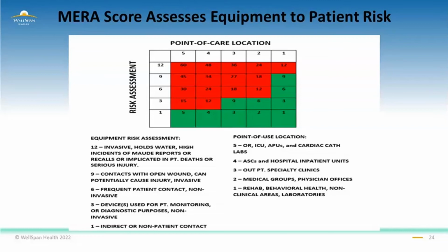First, MERA assesses the equipment to patient risk by choosing the multiple which best aligns with the equipment's components and its physical contact with the patient. Based on our equipment review, we know that the equipment holds water in a humidifier reservoir per the manufacturer's instruction manual. So we begin at the left column of the chart reviewing the categories. We assign the equipment risk number a 12.